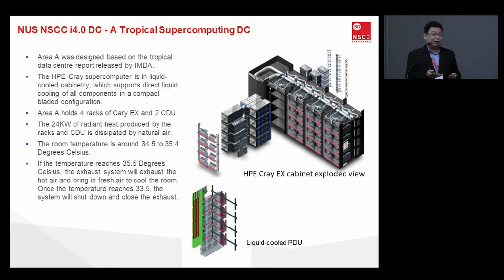To be honest, the system can operate all the way up to 40 degrees. Hence, we start exhausting at 35.5. Why? Because for the dehumidifier to bring down by 10%, the temperature goes up by 2 degrees. So therefore, 39.5 gives me a good 20% of the humidity that I can get rid of before my room starts to overheat. So this is the design of the room. So that's how we take care of the temperature and the humidity within this particular room. All right?